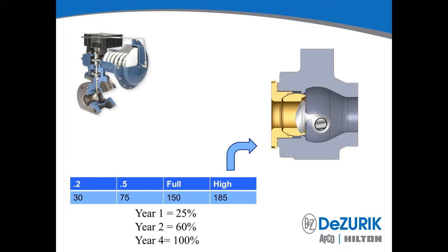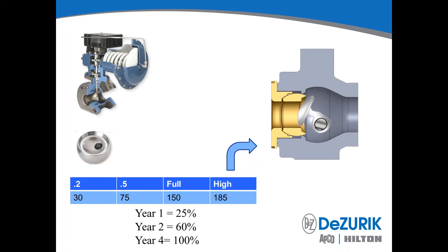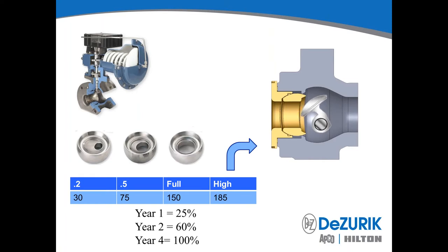Now, if RCVs were installed in place of the globe valves, this is what we would look at. These are the trim reductions in an RCV: we have 0.2 trim, 0.5 trim, full, and high, with corresponding CVs of 30, 75, 150, and 185. For year one you would install the 0.2 trim; year two you would install the 0.5 trim; and so on until you're at the full capacity trim. This is much less expensive than having to change a plug and seat, and much less labor-intensive to change out as well.